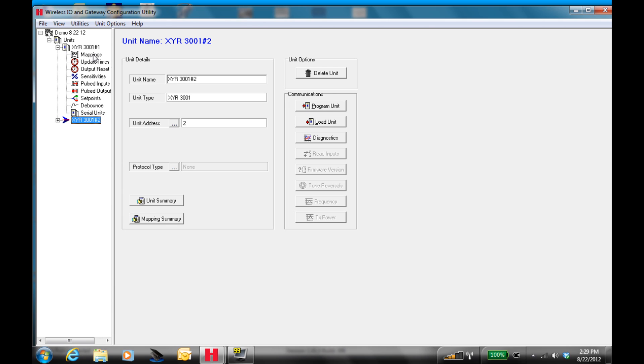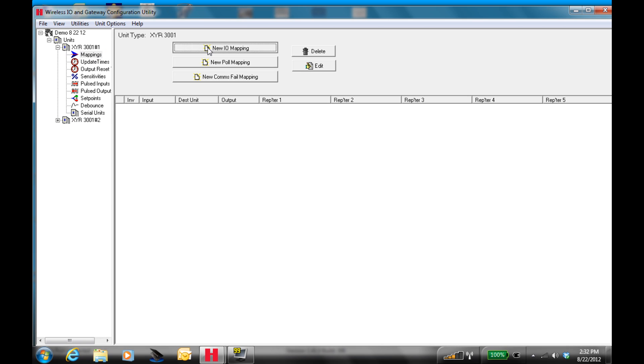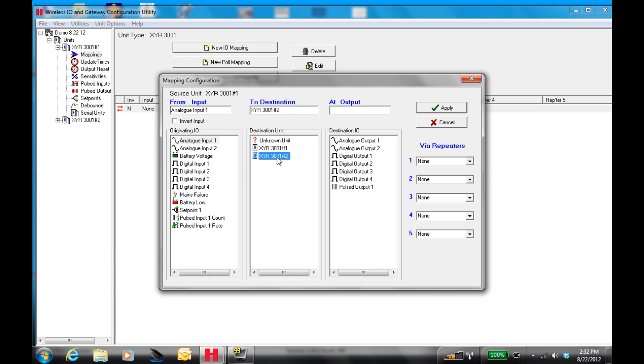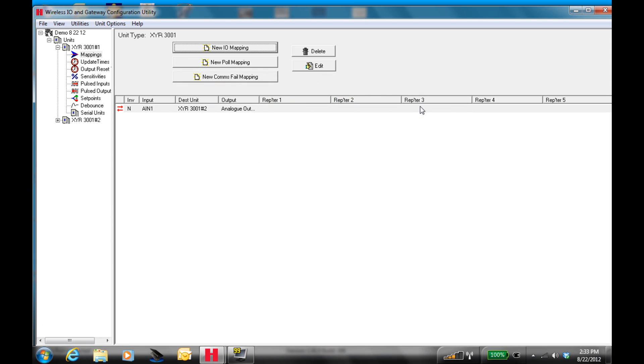You pull your tree down and then you go to mappings. New IO mapping. In this case, I want an analog input from radio number one to drive an analog output from radio number two. So I select the input in radio one — in this case I'm going to select input one. Its destination will be radio two, and I'm going to select analog output one. So now your analog value in unit one will drive the analog output in unit two. Once you've configured this, you hit apply.